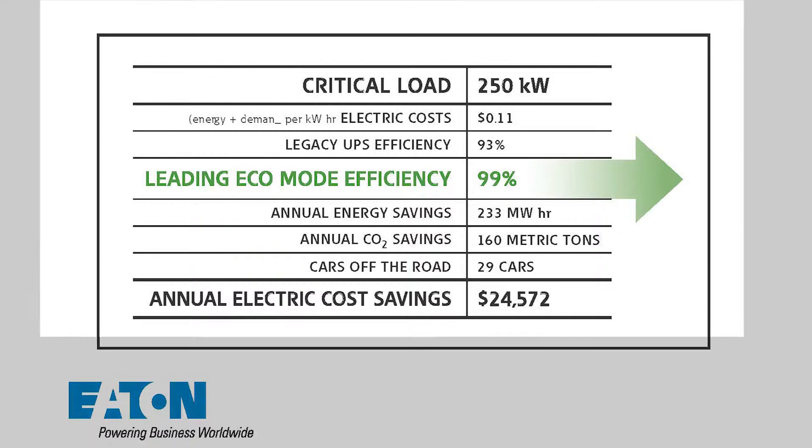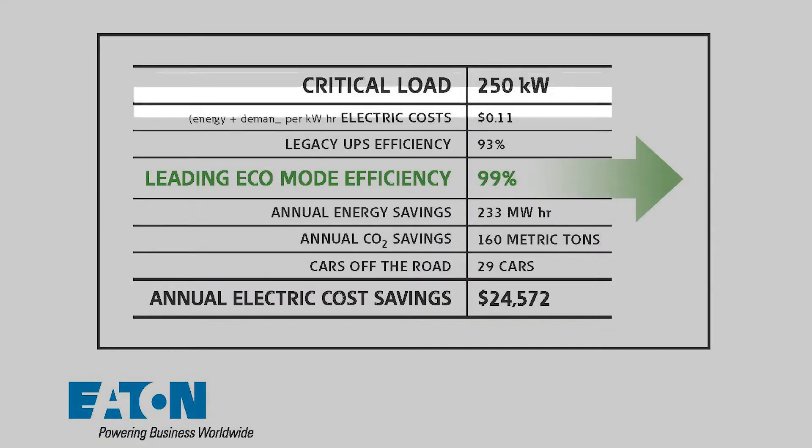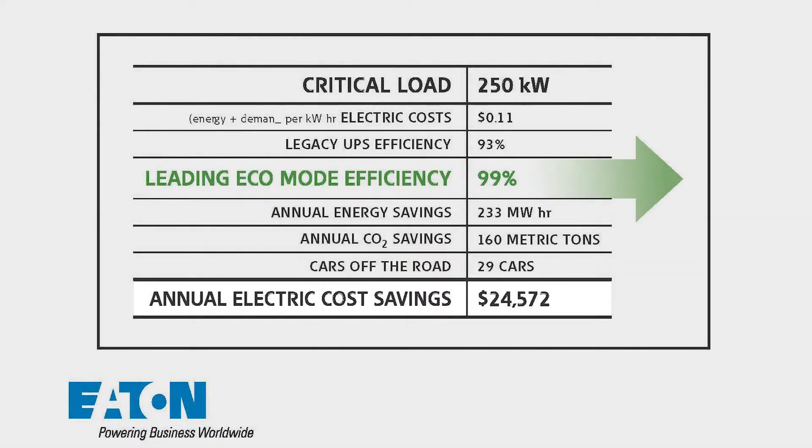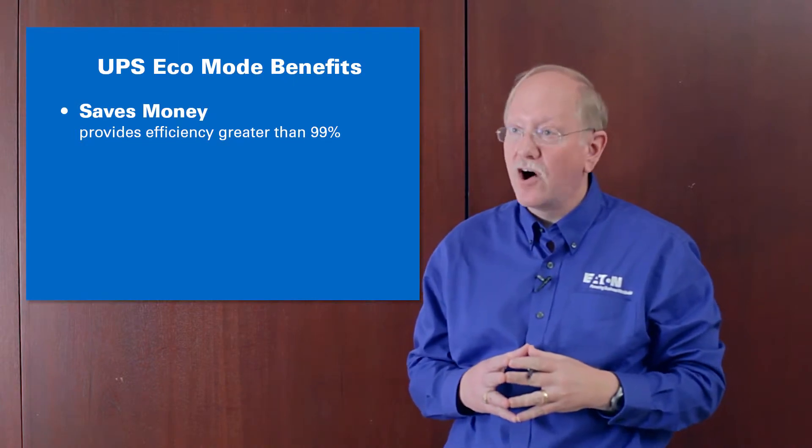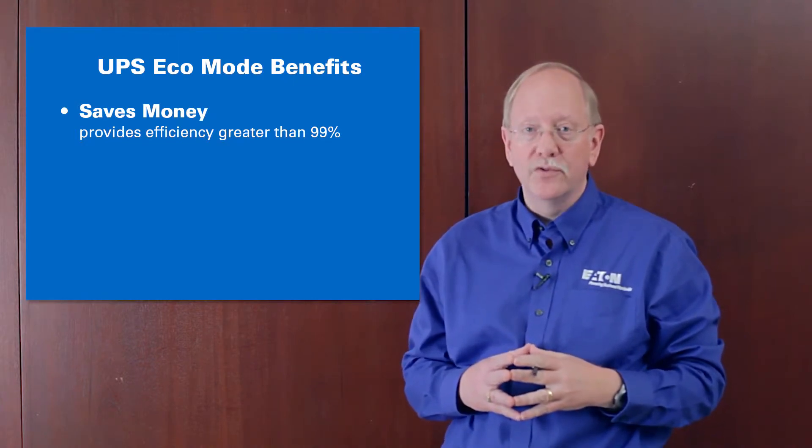Here we have a 250 kilowatt UPS compared against a legacy UPS that's 93% efficient using an eco mode UPS at 99% and the savings at 11 cents a kilowatt hour are $24,500 per year of operation. Significant savings and will actually repay the cost of the UPS within two to three years.